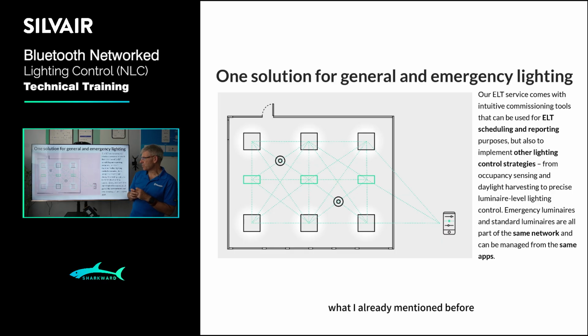What I already mentioned before, this solution has been extended to include emergency lighting testing recently, and this is a very welcome feature from our customers. Comes by default for DALI-based devices. Also for markets where DALI is not popular, like North America, for example, there are dedicated wireless emergency products which are also compatible with the system. So things like exit signs, things like bulkheads, things like twin head emergency lights or spotlights with battery-based drivers and inverters, they are all included.